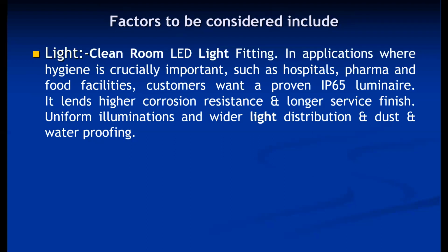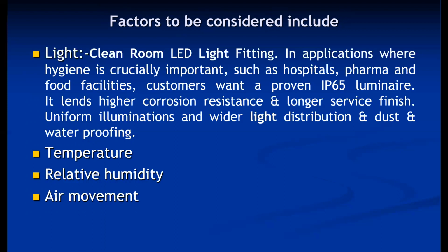So while fitting lights in a clean room, special purpose lights are used, which should be non-corrosive, provide uniform lighting, and be dust free and waterproof as well. Besides, the other factors which are considered in a normal air conditioning system, like temperature, relative humidity, air movement, and purity of the air. Mainly the purity is the major concern in a clean room, that is particulate contamination, and depending upon the concentration of contamination, the various classes of clean room are designed.